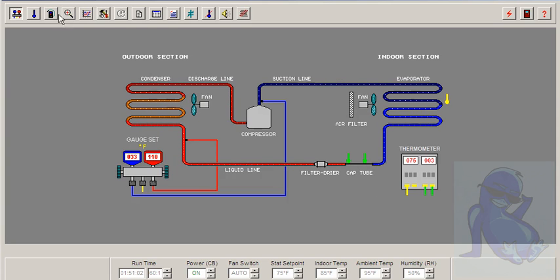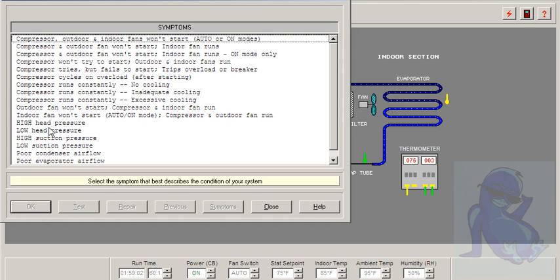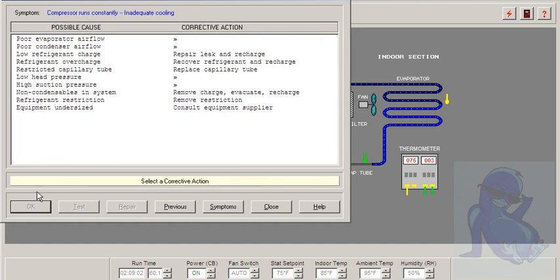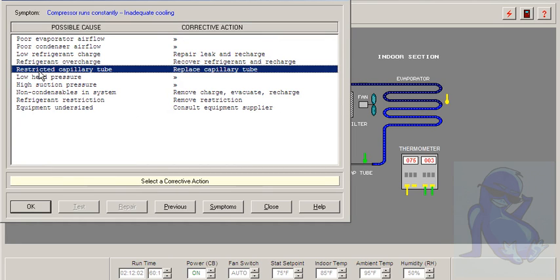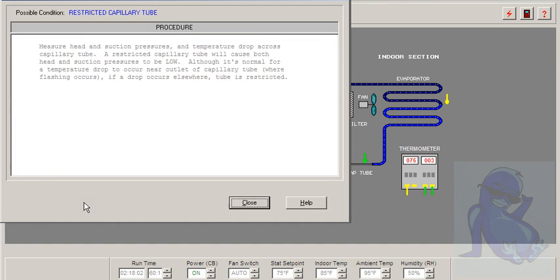Let's see what kind of solutions it's going to give us. It's inadequate cooling, that's for sure. We have low head pressure. We do have that. Restricted cap tube. Let's OK and test.